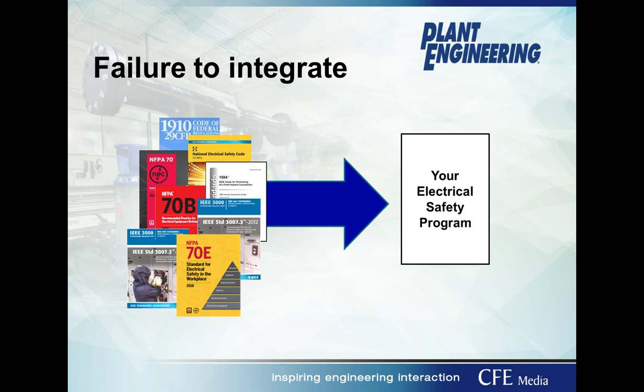Another pitfall is the failure to integrate the relevant codes, regulations, and standards into your own unique, customized electrical safety program for your facility, company, or organization. The pitfall I see many people fall into is thinking we comply with all OSHA regulations, or we use NFPA 70E, as if that is our electrical safety program. The regulations and standards are not an electrical safety program by themselves. They are there to provide guidance on what your program needs to contain, and it's more than what's in any one code, regulation, or standard.